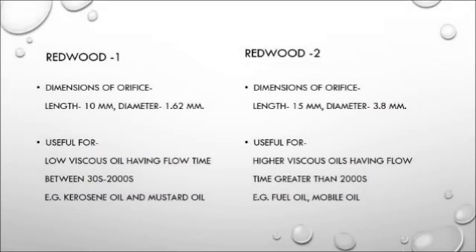Now we are going to tell you about the differences between the Redwood 1 and Redwood 2 viscometers. The dimensions of the orifice of the Redwood 2 viscometer are greater than the Redwood 1 viscometer, both in length and diameter. The length of the Redwood 2 orifice is 15 mm, while the length of the Redwood 1 orifice is 10 mm. The diameter is larger in the Redwood 2 viscometer at 3.8 mm, and the diameter of the Redwood 1 viscometer is 1.62 mm.